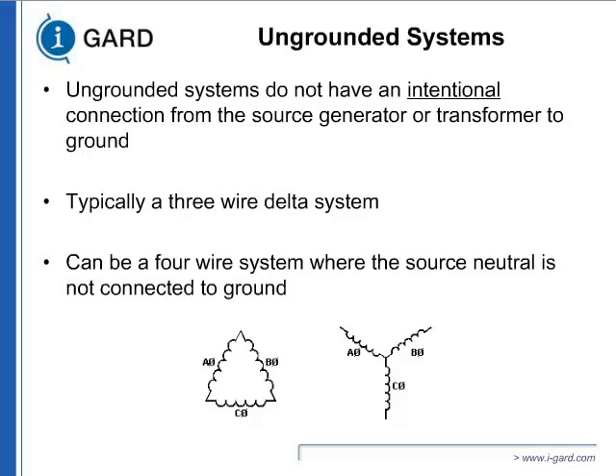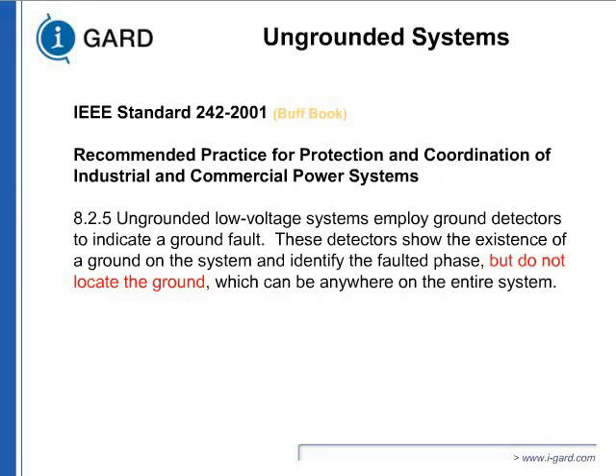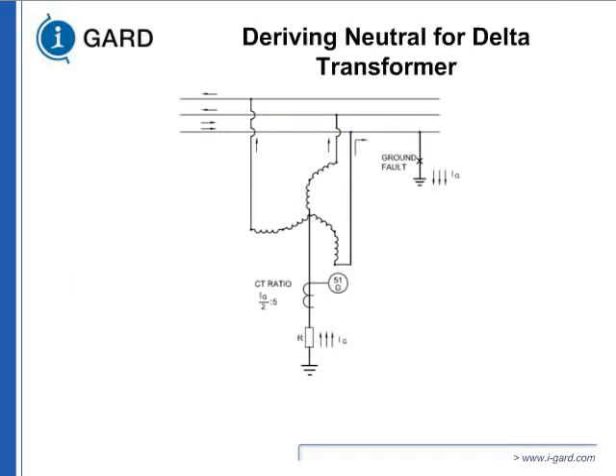Okay. This is a quote from IEEE Standard Buff Book. You'll see that ungrounded low voltage systems apply ground detectors to indicate a ground fault. That's all they can do. They can show whether there is a ground there or not and which phase is grounded. But they do not have any way to locate the ground fault. Only way a ground fault could be located on a delta system, or still can be located most of the time, except for some technology people claim they can do that, is shutting circuits on and off. So what do you do if you have a delta transformer? You derive a neutral to put a grounding, and that's what I just wanted to get you aware of this, so we'll keep on, then the technology will follow later on.